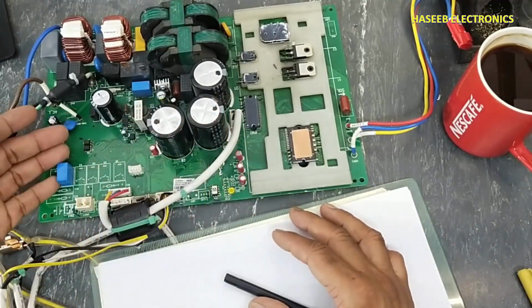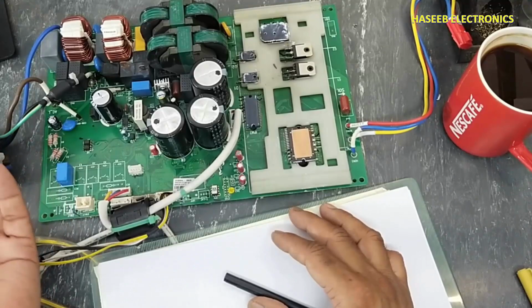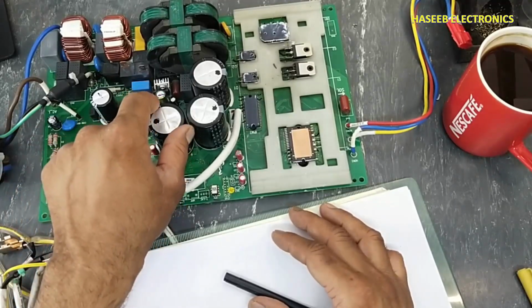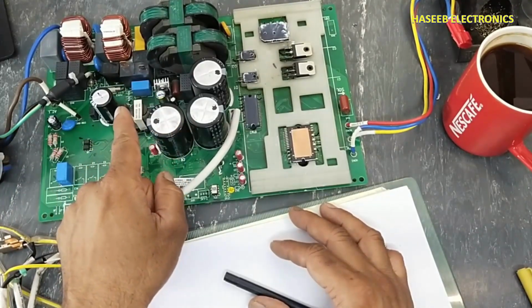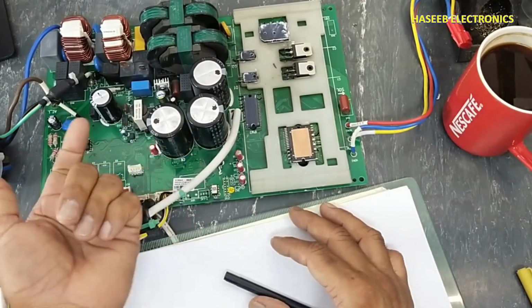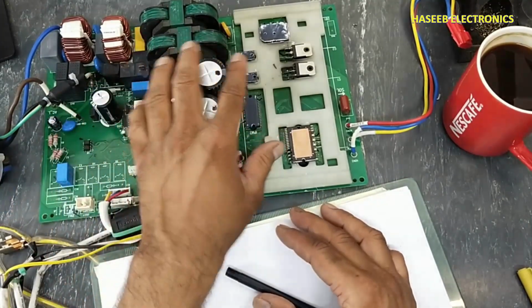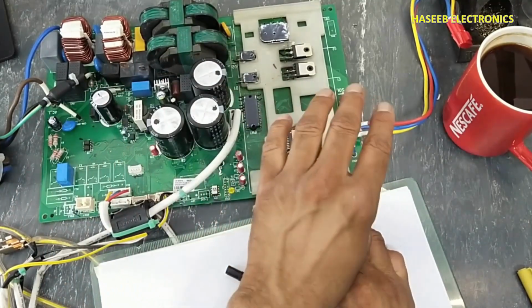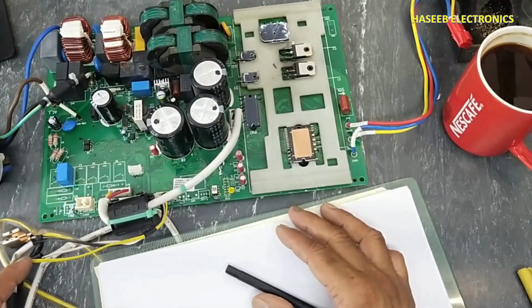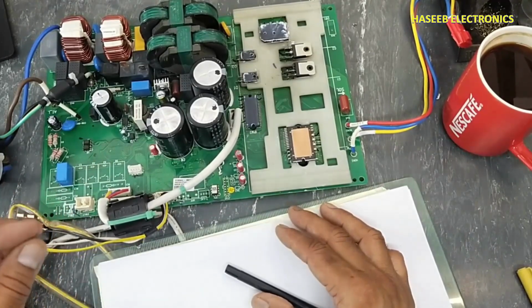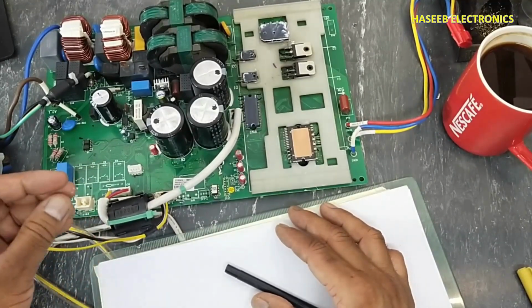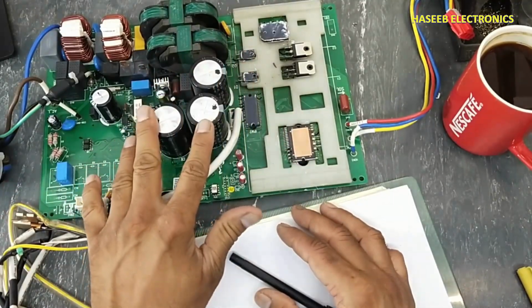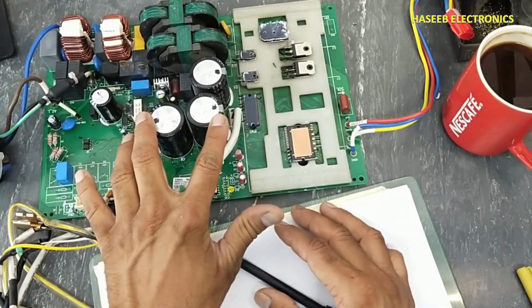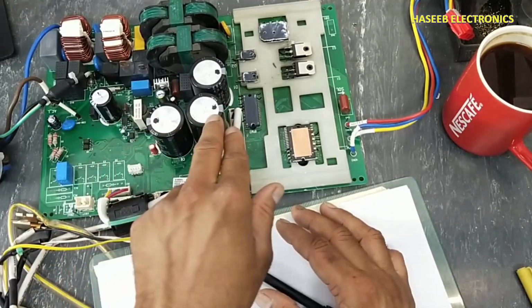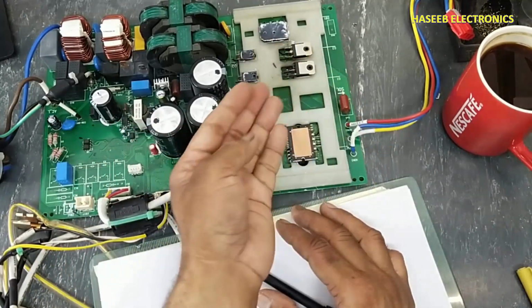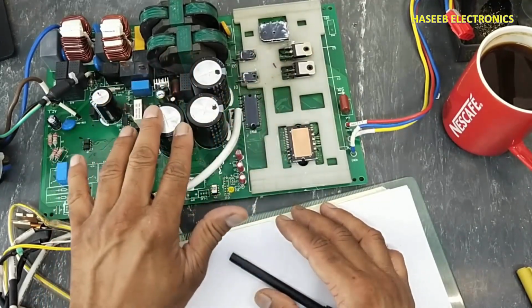When it receives an order from the master unit, that is the indoor unit, this board is the slave. The master board or master microcontroller is the indoor unit board. The indoor unit will send a command to turn on the compressor. It will monitor different pressures, temperature, ambient temperature. It will check the voltage value. If the voltage is lower than the rated value, it will give an order to this PFC section to boost up the voltage. It will maintain the voltage here.